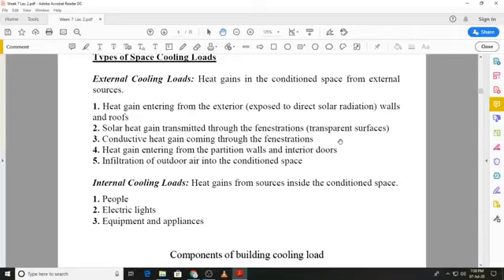cooling load estimation. Then we move on to internal cooling loads, and the internal cooling loads are due to three sources: occupancy or people inside the conditioned space, the operation of electrically operated lights, and also equipment and appliances. People are a source of both latent and sensible load, because we are exchanging heat with the environment by convection and by radiation. Then moisture also is being evaporated from the skin of a person, and when you breathe out, the breath also contains water vapor, so that leads to both a sensible and latent load.